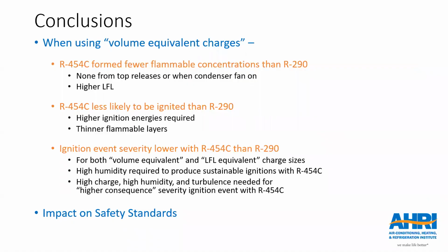Next slide, please. So what did we learn from this? What were our conclusions? Well, when using volume equivalent charges, 454C formed fewer flammable concentrations than propane, and none from top releases or when the condenser fan was on. And this is largely attributed to the higher LFL of R454C. 454C was also less likely to be ignited than propane, and this is largely due to the fact that higher ignition energies are typically required to ignite an A2L than an A3. And the ignition event severity was lower with 454C than with propane. This was both for volume equivalent and LFL equivalent charge sizes.